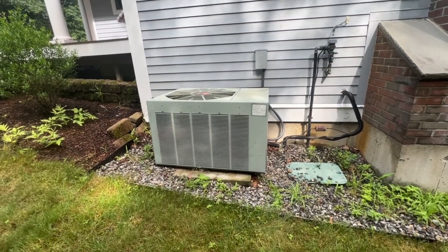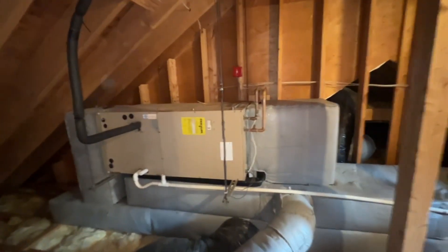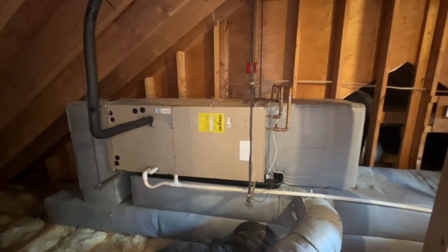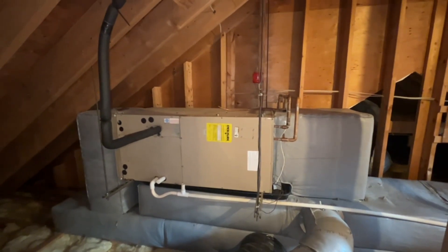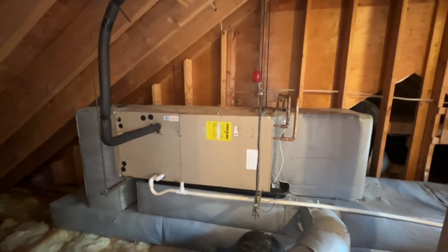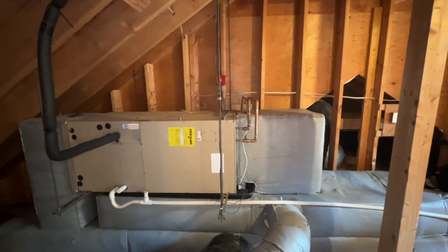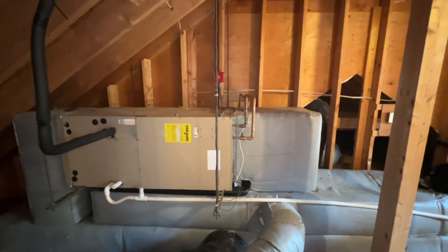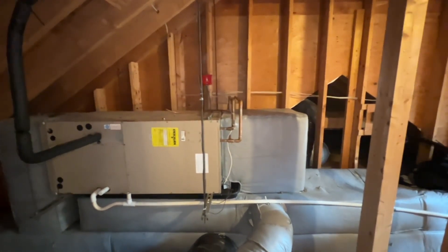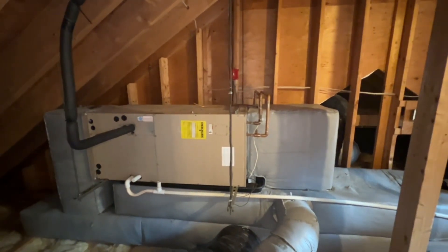I'll get you some more video and photos as we begin this journey today. So here's the attic air handler now. This coil in here cannot handle the pressures of the R410A and cannot be replaced because the evaporator coil would not fit inside the box. So unfortunately we have to change the whole air handler to an ECM air handler, and then we're going to have to add a stand-alone hydrocoil for the hydronic heating to continue to work when it reaches the outside air temperature of 30 degrees to meet the MassSave requirements.